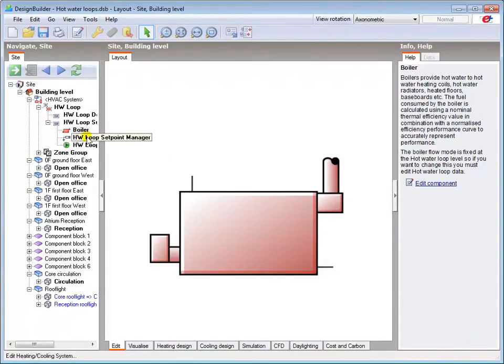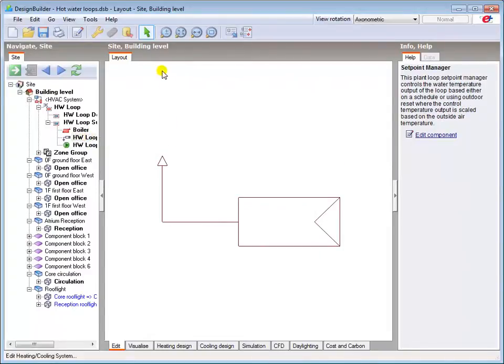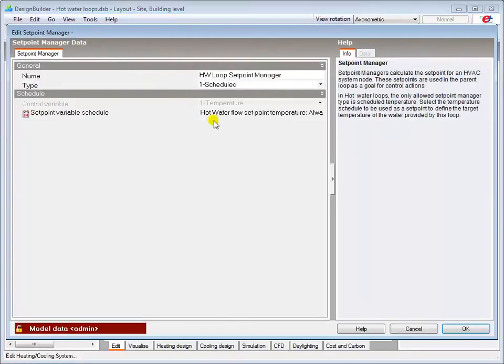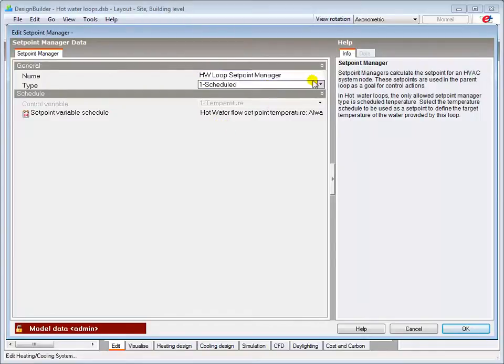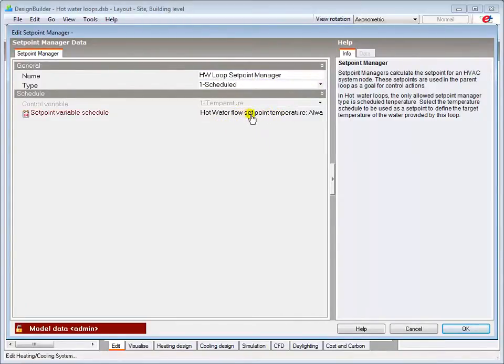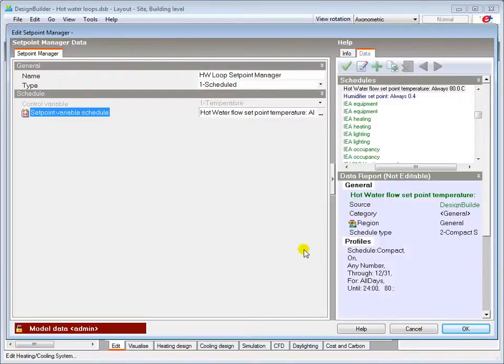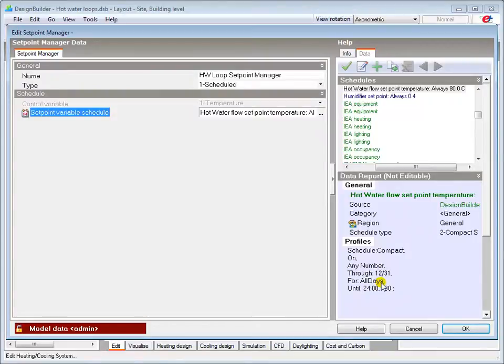The supply sub-loop includes a setpoint manager, enabling you to define a temperature setpoint and a schedule during which that temperature is used. The setpoint manager is set up by default to control the hot water flow temperature to a constant 80 degrees C. You can load a different compact schedule if desired. Note that this is a temperature setpoint schedule, so the setpoint value is always in SI units, i.e. degrees C.